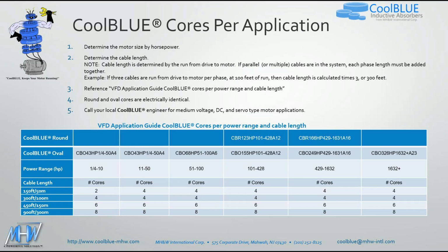So if you have 3 cables for each phase, you're just going to multiply your run by the number of cables. Otherwise, if it's just a single cable system and your motor is 100 feet away, your cable length would be 100 feet. You would then reference the VFD application guide, CoolBLUE cores per power range and cable length as shown below. And these application guides are available through DREISILKER.